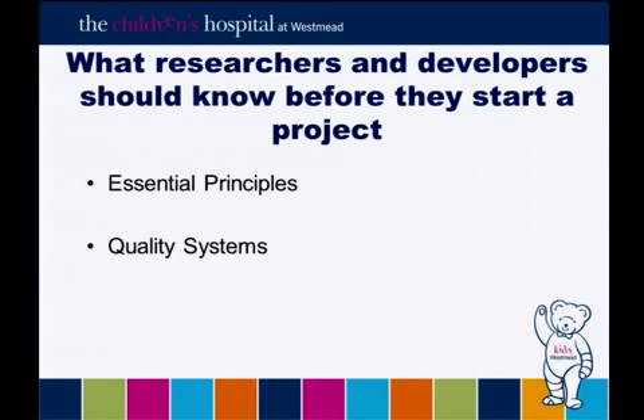So if you go out and do clinical trials to prove that the device works and it's safe: prior to 2007, all you had to do was prove that the device was safe. So you could say, I've built this device that makes you live to 1,000 years if I implant it in you, and you could sell that as a medical device, provided it didn't hurt you, okay? It didn't matter if it didn't make you live to 1,000 years, give or take a few. As long as you could prove that it was safe, you could still sell it as a medical device. In 2007, they started to bring their emphasis back into clinical evidence. So if you had an advertising claim or a therapeutic claim that it kept you alive for 1,000 years, you had to do long-term trials to prove that it did. I think they're still ongoing, those trials.